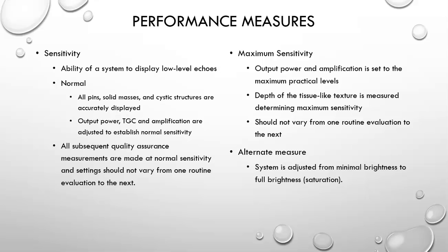To determine maximum sensitivity, the output level and amplification is set to, and I'm going to quote this from the Edelman book, output power amplification is set to maximum practical levels. Depth of tissue-like texture is measured to determine maximum sensitivity, and this should not vary from one routine evaluation to the next. So that's out of the Edelman book.